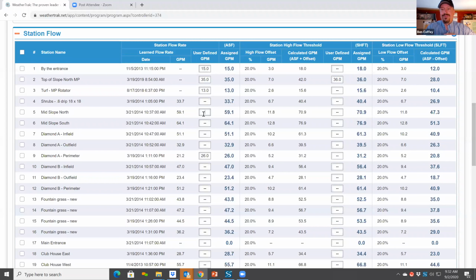And it'll eliminate a lot of what guys see as false alerts, right? That 1 gallon per minute over. Because if it's right on the edge, as soon as it tips over the threshold, that alert is prompted. And it's pretty surprising what the flow sensors do pick up, and so it's easy to disregard 1 gallon a minute, but you definitely don't want to just blindly increase your threshold. It's just over 1 gallon, because it could just be one nozzle that blew off, and it's taking you over the limit now. But it's a very visible issue to your customer, right? That one that's just barely over the limit is shooting 20 feet in the air. That's not something you want to just miss.